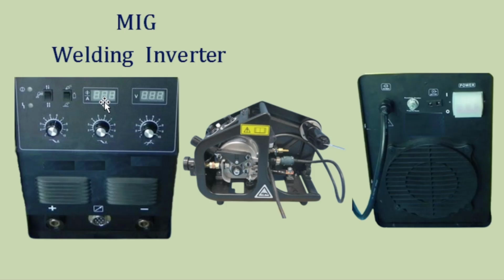This display shows welding current and this display shows welding voltage. These 2 potentiometers are for crater current and voltage setting. Another potentiometer is given for inductance setting. On the lower side, 2 OKC terminals are for welding positive and negative power supply connections. The socket is given for connecting interconnection control cable to wire feeder. Wire feeder is so-called dumb wire feeder because no intelligent component like PCB is mounted in it. Positive power cable is to be connected from power source to wire feeder.